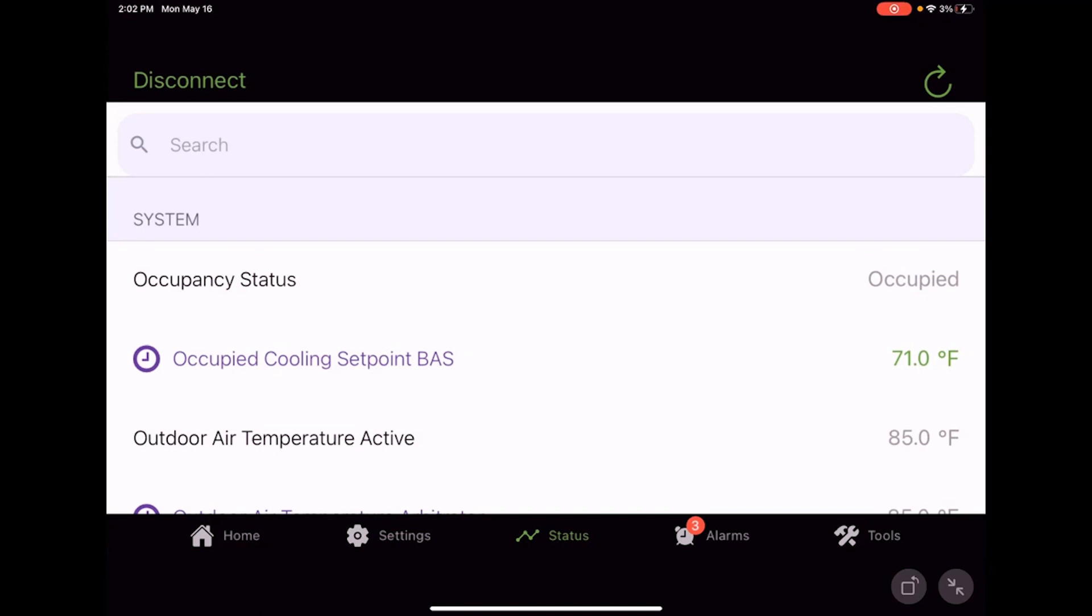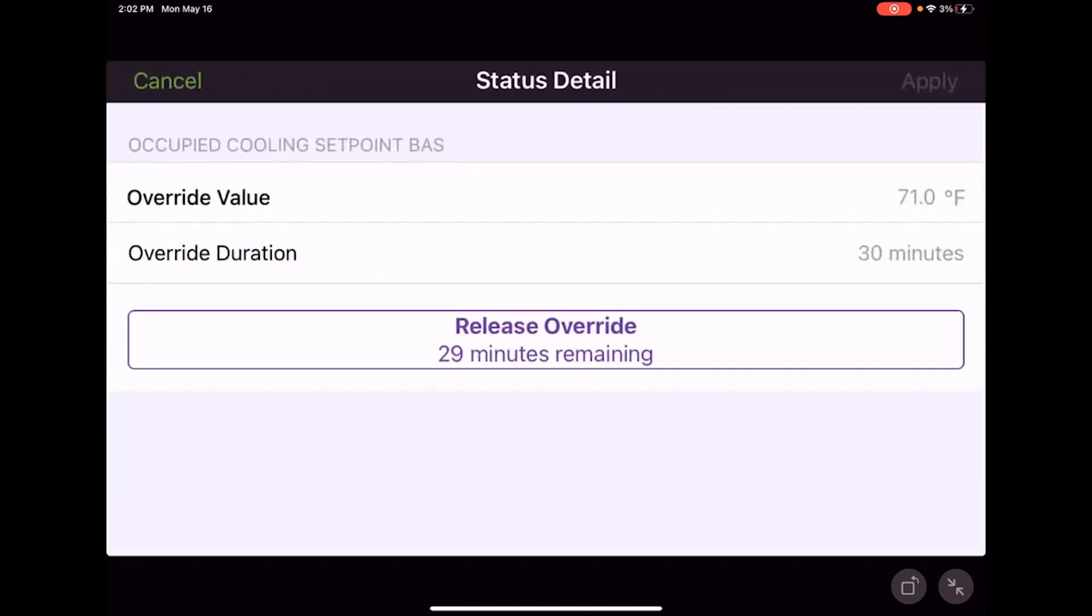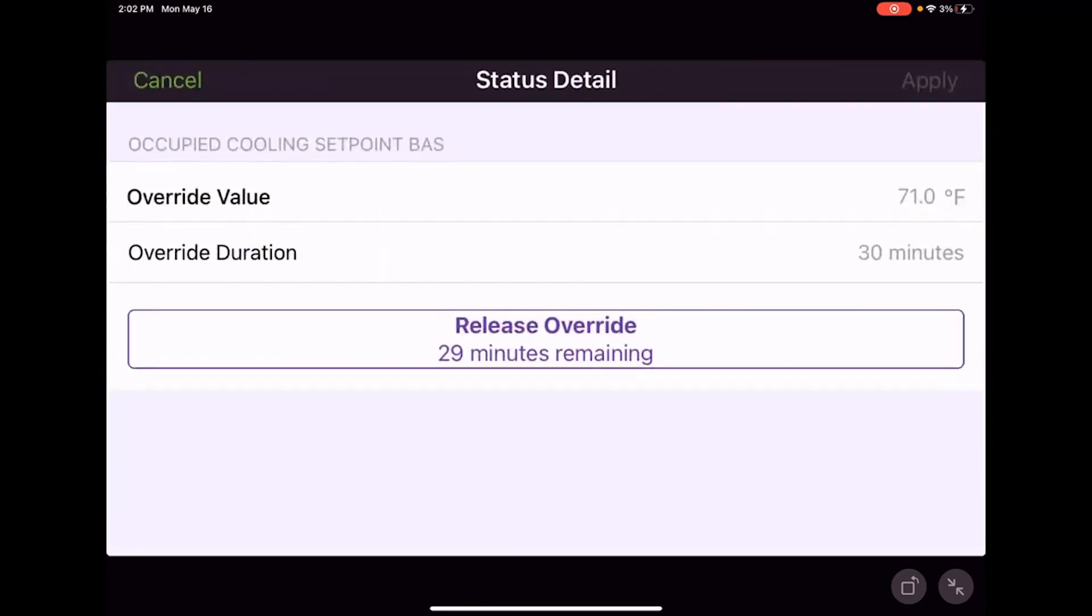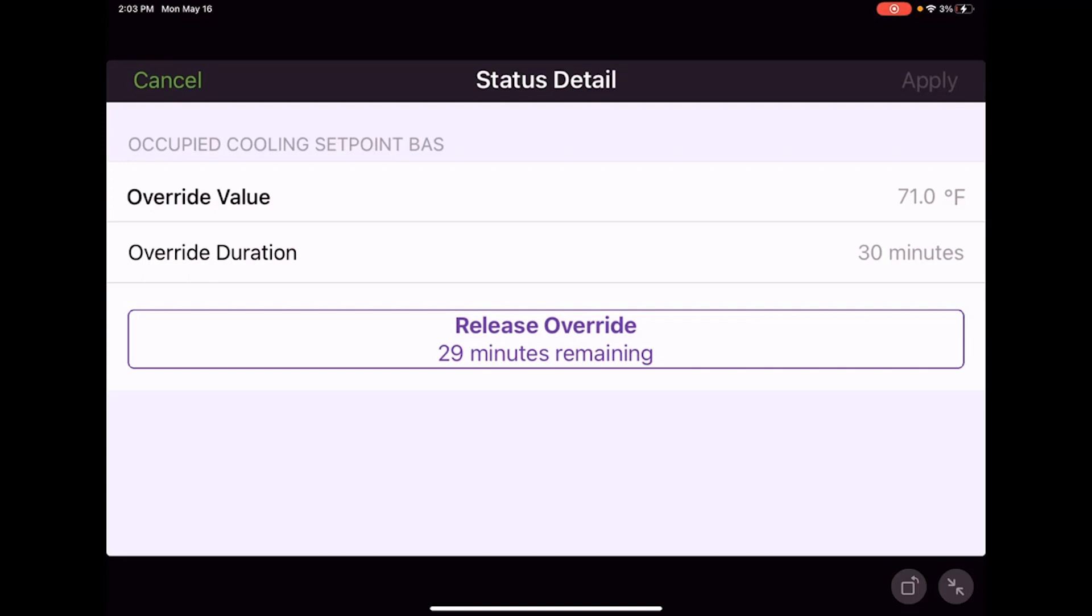Whenever you have a value where the name is in purple, so in this case occupied cooling setpoint BAS, and then we got the green text next to it so we can override it, what that means is we're going to make a temporary override for 30 minutes. Once 30 minutes has gone by, that unit is going to release back to its default value. So it's kind of important to know that if you come in and you override something like this occupied cooling setpoint BAS, it's a timed or temporary override.